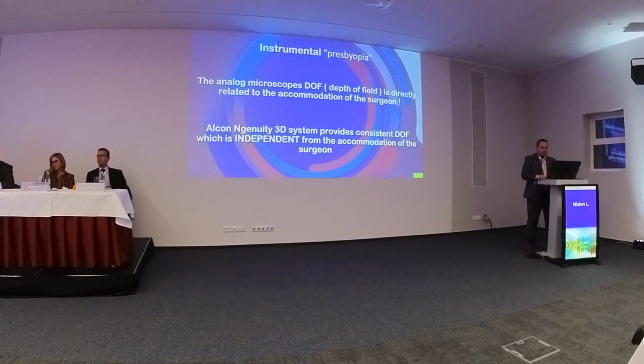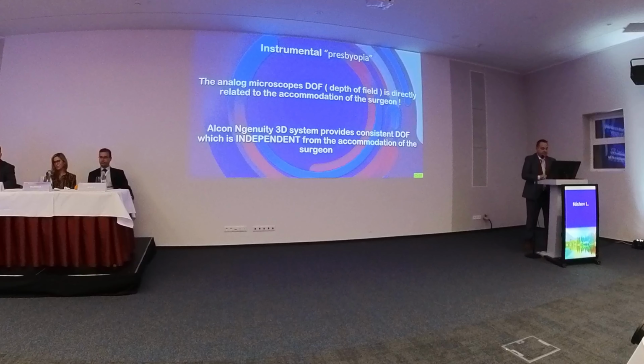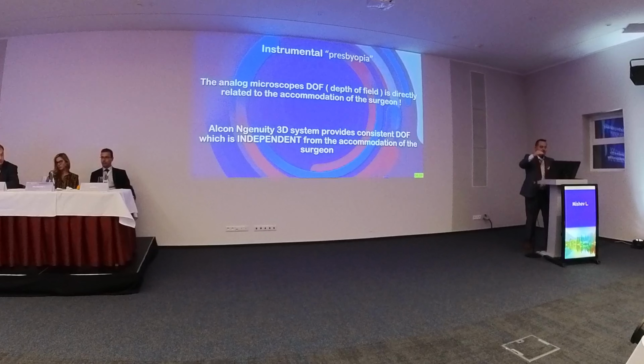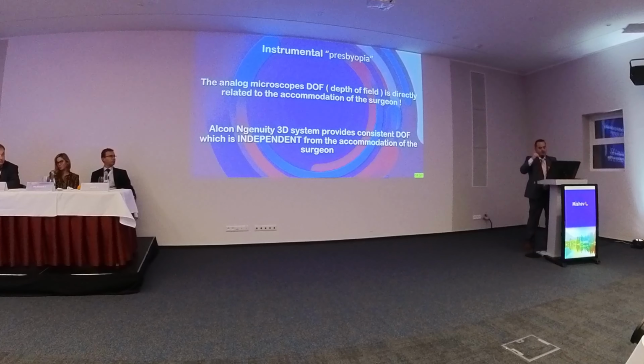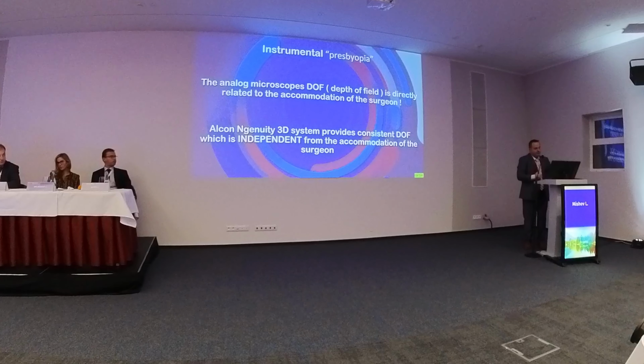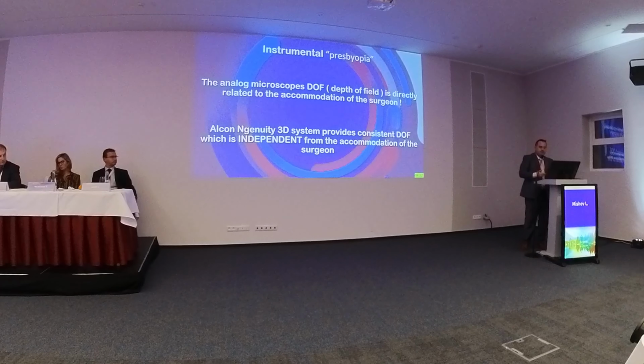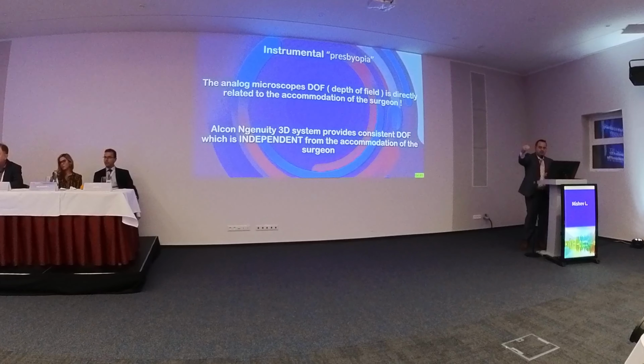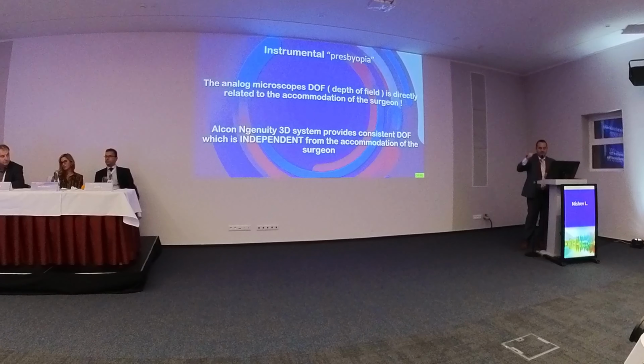There is another thing which is absolutely related to the presbyopic age, for some of us who are presbyopes already. The overall depth of field or depth of focus of the microscope depends on the accommodation of the surgeon, meaning that younger surgeons will have more depth of field than surgeons of presbyopic age. When you have an Ngenuity system and you are looking at the screen, you are actually using your far vision and you are independent from presbyopia.